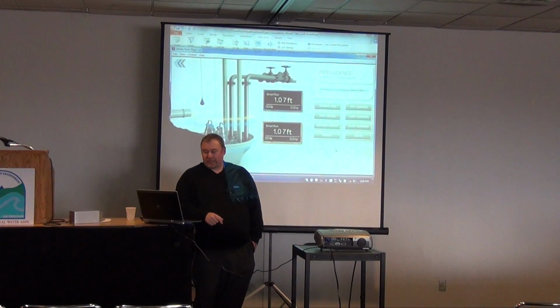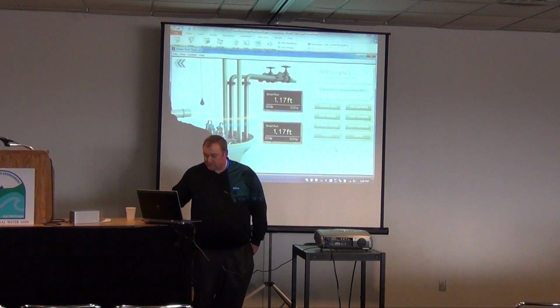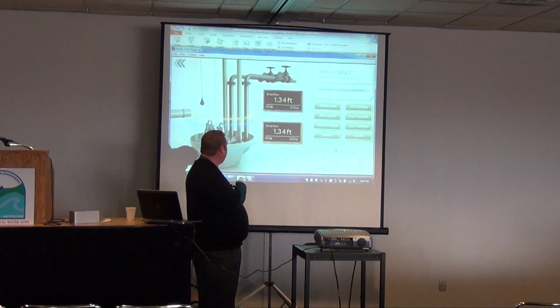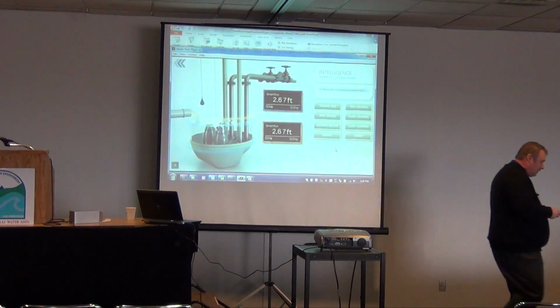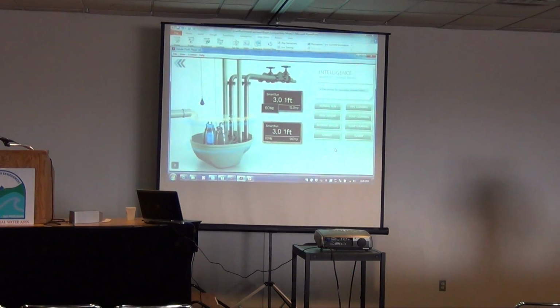But at that point, those rings that you see there, the blue and the yellow, I want to point out that these units randomize their start. And it's all done within about 9 inches of each other. The advantage of that is for all of you that have grease buildup in your stations, you get a grease ring because that start point is always the same, isn't it? Typically, if you have a float or a start point set on a transducer, that ring ends up in the same place.